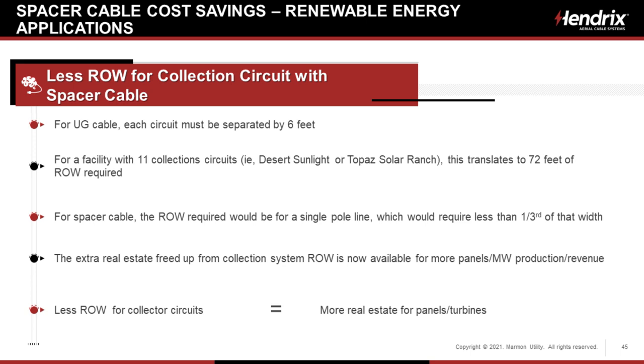And I said also that we have less right of way for the collection circuit with spacer cable. If we're looking at underground cable, and this was pretty obvious when I showed you the Desert Sunlight project, each circuit has got to be separated by 6 feet. So for a facility with 11 collection circuits, that translates into 72 feet of right of way required. For spacer cable, the right-of-way required would be for a single pole line, which requires less than one-third of that width. So again, the extra real estate freed up from the collection system right-of-way is now available for more panels and megawatt production.